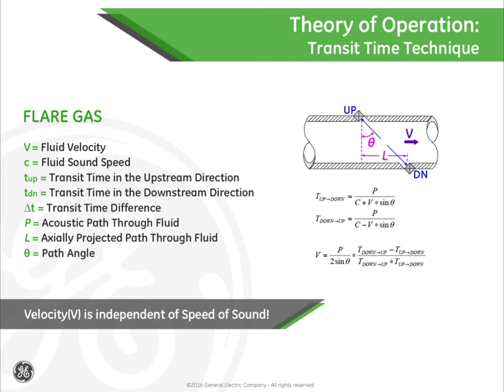If there is no fluid flow present in the pipe, then T up is equal to T down, and the transit time up minus transit time down is equal to zero. However, when there is flow in the pipe, the transit times are different, and this difference, or delta T, is proportional to the fluid flow in the pipe. Without getting too deep into the math, since we're measuring delta T, the flow velocity is actually independent of the sound speed of the fluid. This is extremely important when making a flare flow measurement because the sound speed of the fluid in the pipe is changing due to changes in molecular weight, temperature, or pressure. An additional benefit of ultrasonic meter technology is the ability to measure fluid flow bidirectionally.